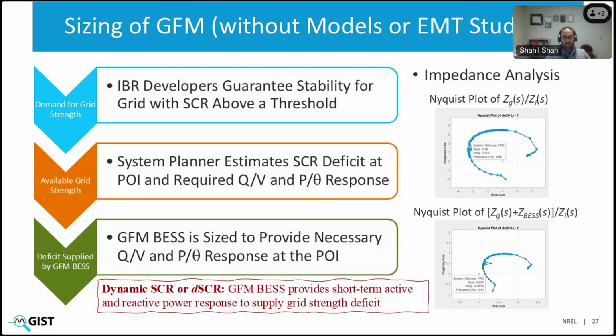Now, system planner estimates, okay, if I'm getting this much amount of IBRs within this region, and if they demand a particular grid strength, let's say an SCR of 3, what is the actual grid strength we have in the system? And that determines what is the available grid strength. And based on the difference between this demand for grid strength and available grid strength, we find out the SCR deficit. And that SCR deficit can be translated to how much Q by V, or basically var per volt, as well as watts per degree, or P by theta response, we need for these IBRs to see the grid as if it is above that threshold requirement.